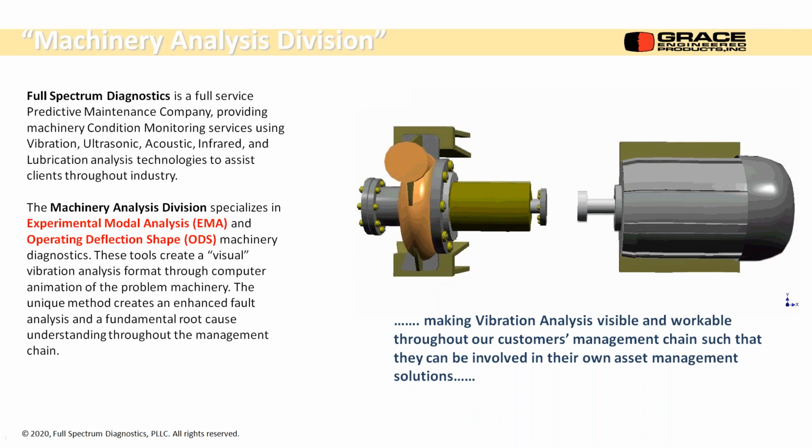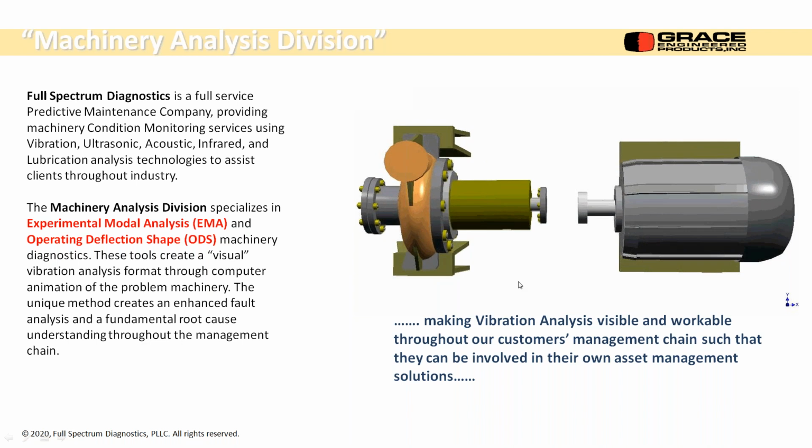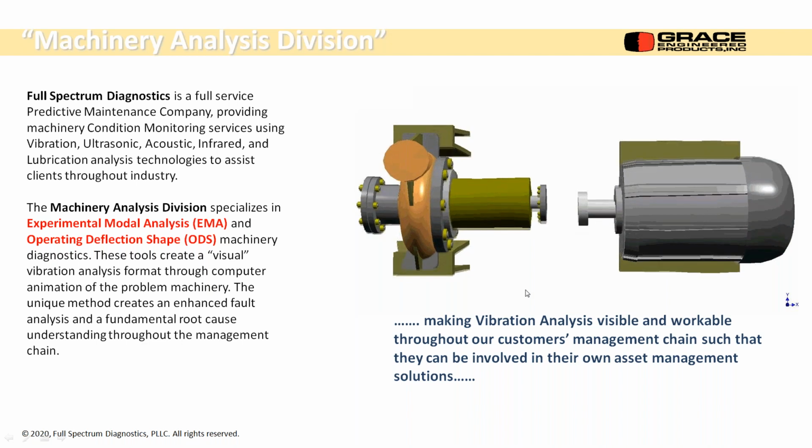This was a refinery pump in Wyoming. And you can look at it and you can say that it doesn't look right. It looks like it's out of phase with the motor and something's goofed up in the coupling. Everybody sees it right away in an animation.